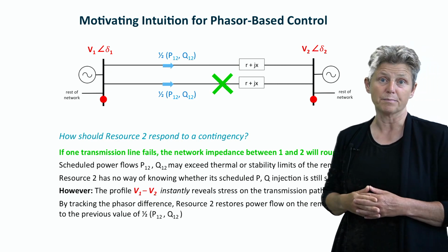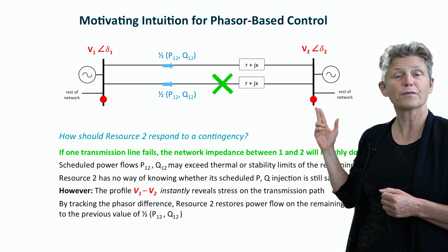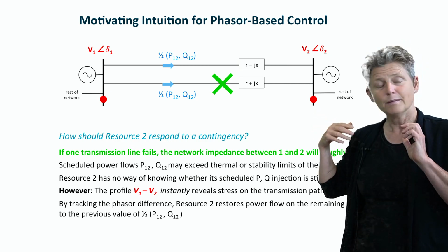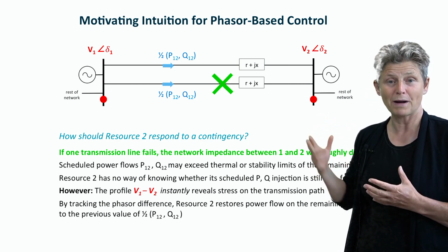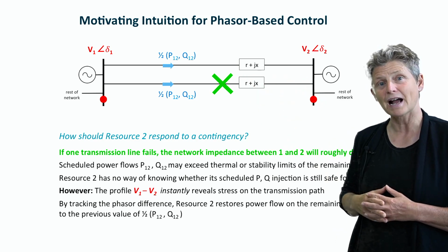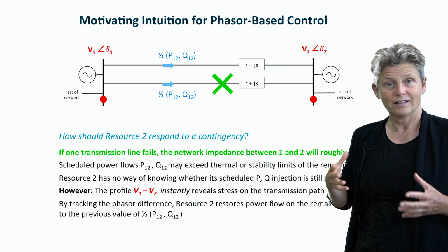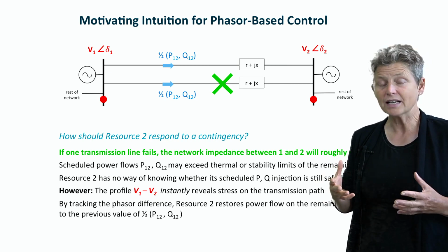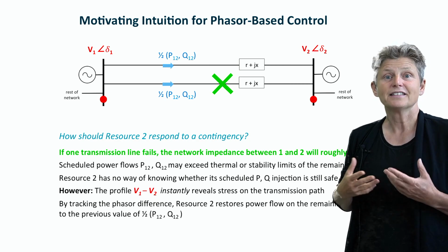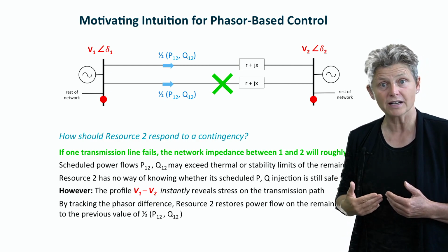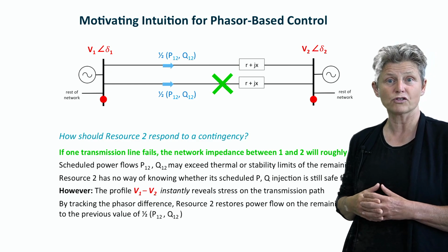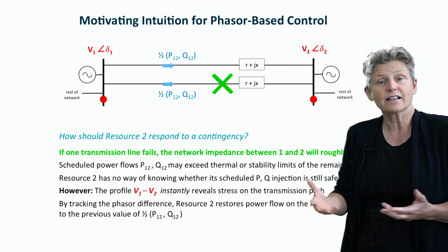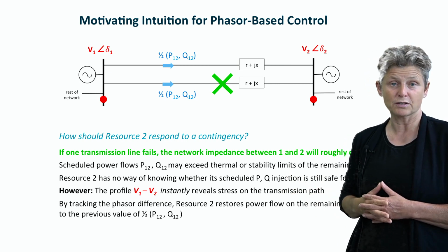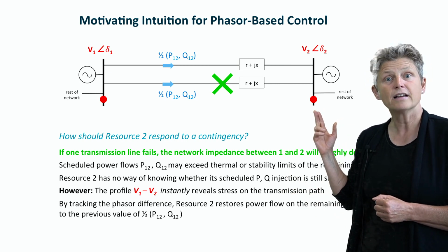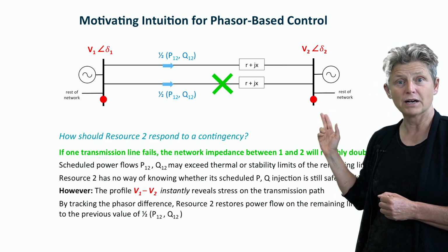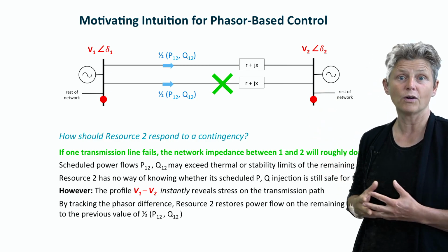And it buys us time. It may not be economical for the resource at this location to be bending over backwards to produce so much more power to drive this phasor difference back, but after a few seconds or even minutes, the supervisory controller can take charge of the situation, can re-optimize based on more detailed information about what just happened, and can reallocate or redispatch the power flow, then issue a new target for bus 2, having taken into account all the available information.